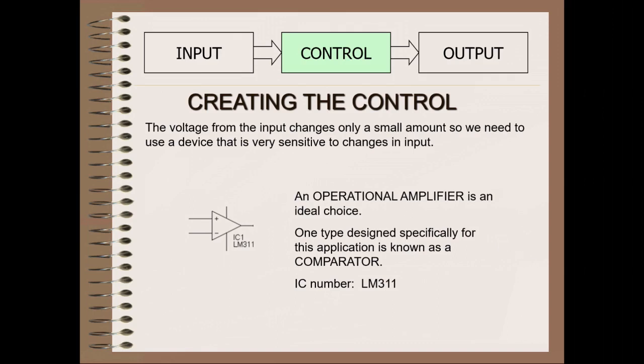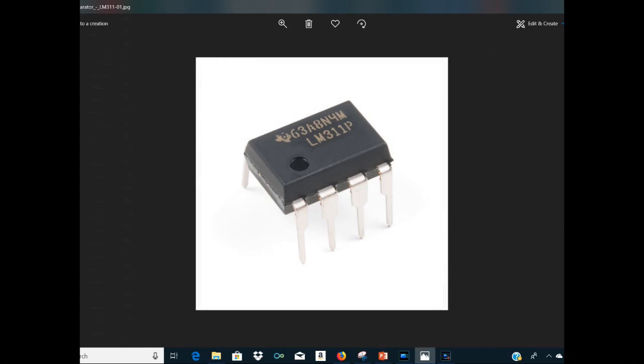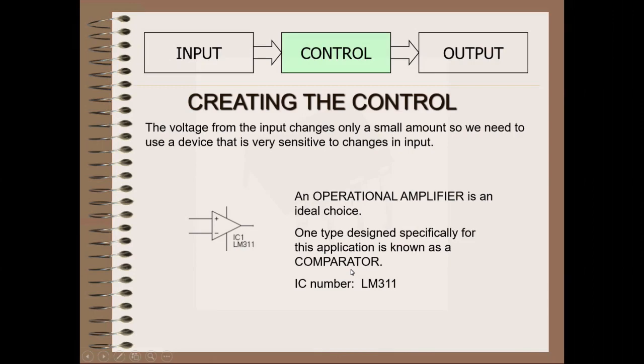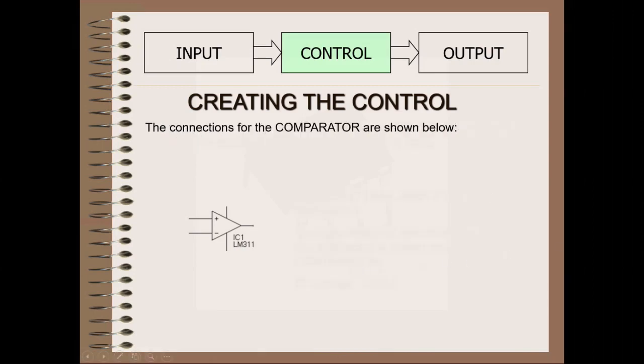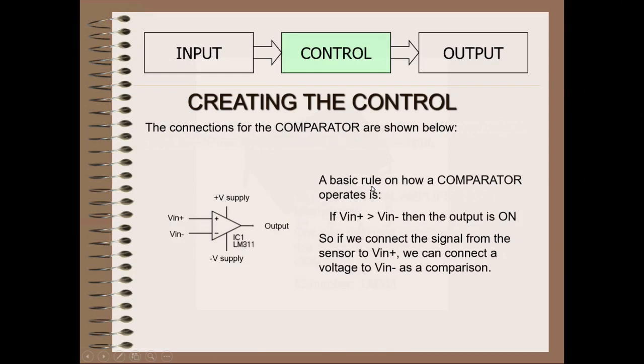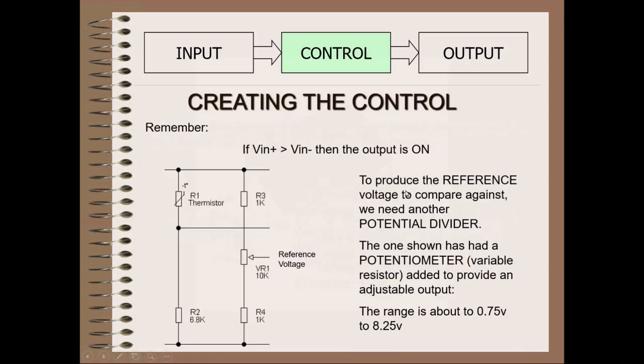The one type we're using here, specifically designed for this application, is known as a comparator. This is what one looks like. The word comparator means to compare, and it's what it's going to do here in a moment. The connections for the comparator are shown. The rule on how a comparator operates is: if the voltage in positive is greater than the voltage in negative, then the output is turned on. So we're looking at the diagram, voltage in positive right here and voltage in negative. If we connect the signal from the sensor, the thermistor, to the voltage in positive, we can connect a voltage to voltage in negative as a comparison. To produce this, we're going to be creating a reference voltage to compare against.